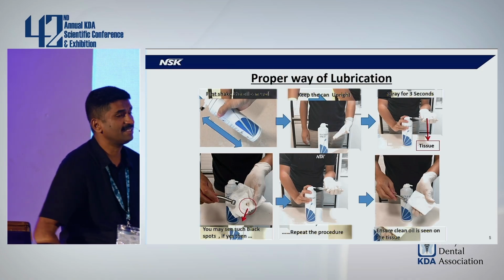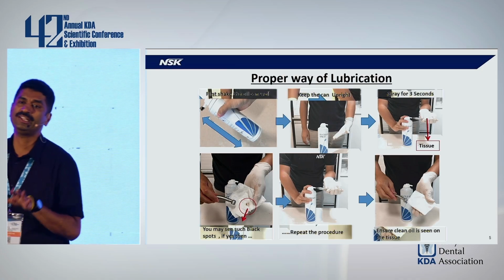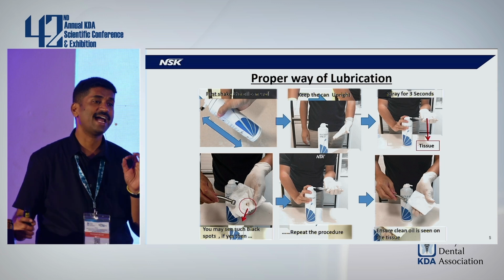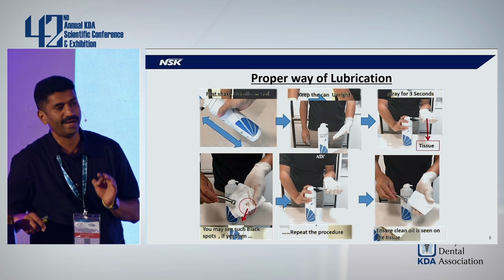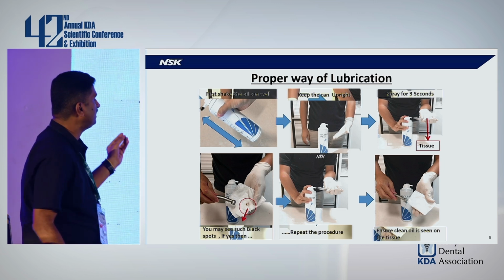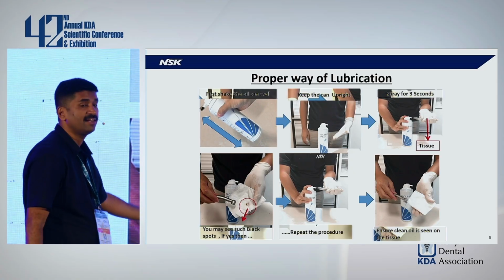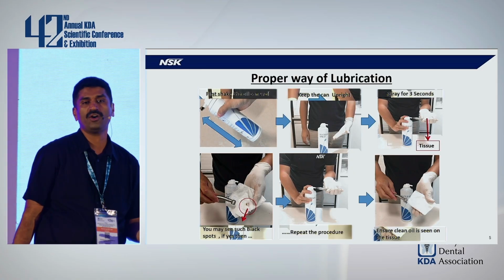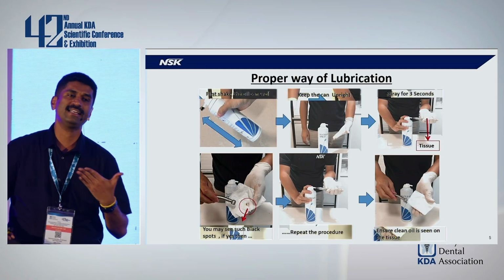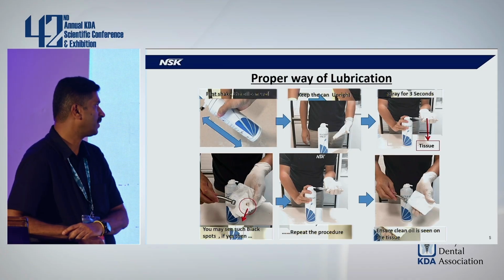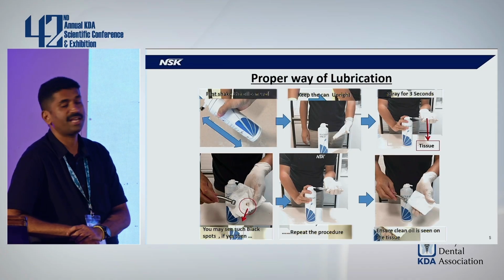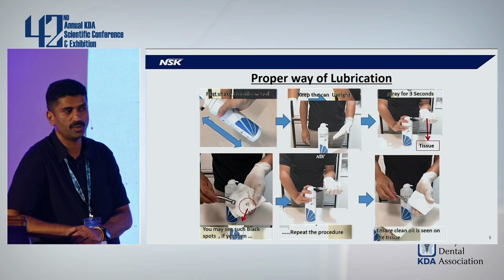Now, this practice, if done properly, then only you're sure that your handpiece has been lubricated well. Unless and until the oil comes out from the head as clean oil onto the tissue paper, only then is it properly lubricated. Okay? So this is the proper way of lubrication, which we recommend you to do.